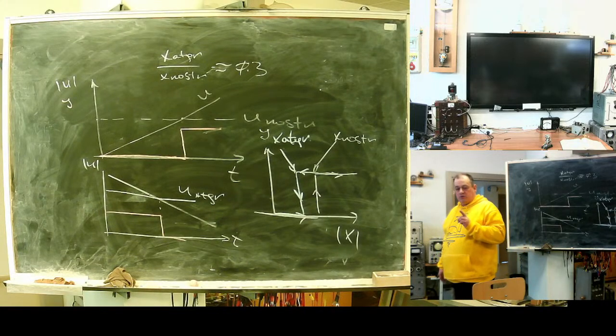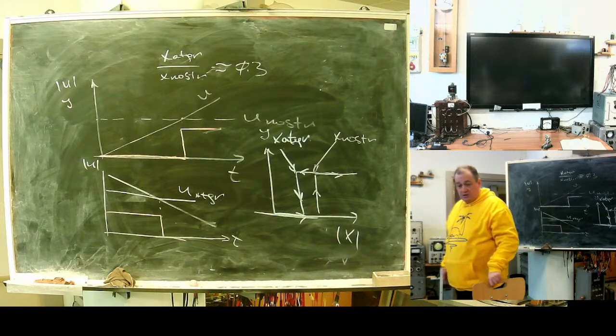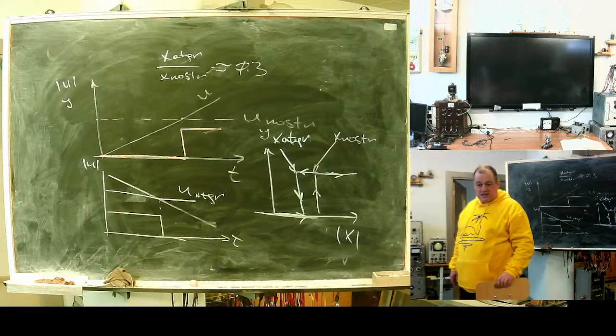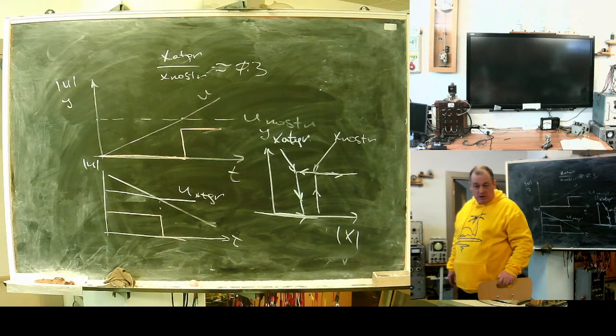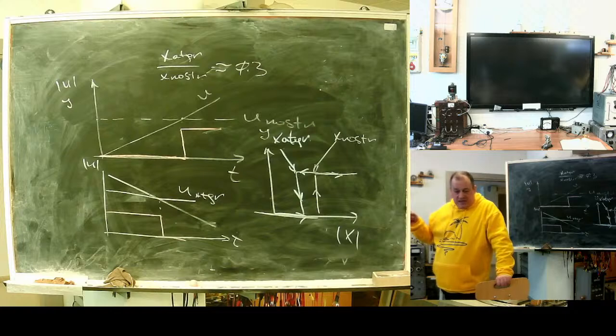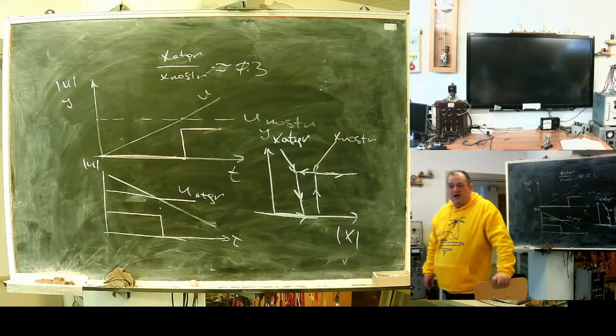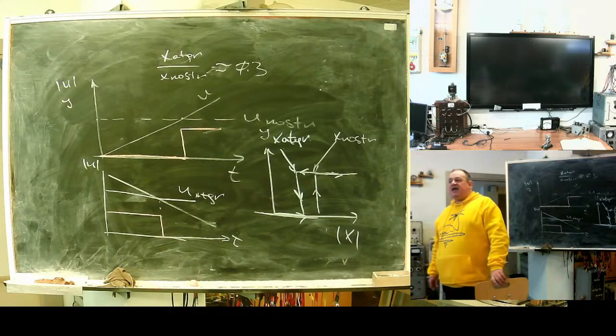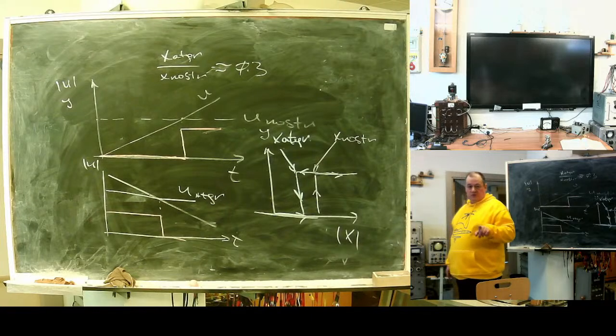There are two points in time. The point when all this logic, watching the current, decides: oh, the current is too much, we need to clear the fault, we need to disconnect the line. And the moment in time when the actual signal to the circuit breaker is sent. You understand that all this logic needs some time to do something. So there are two moments: the start or pickup moment, and the trip moment itself, when the output signal is sent. They are not the same. There is some time between.